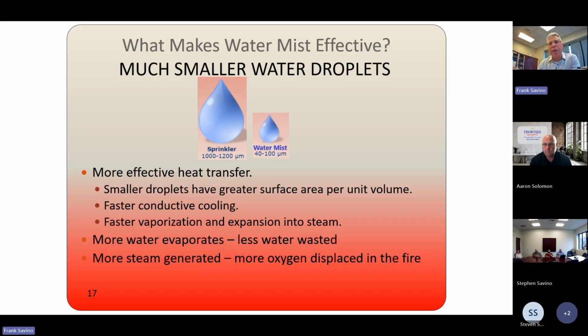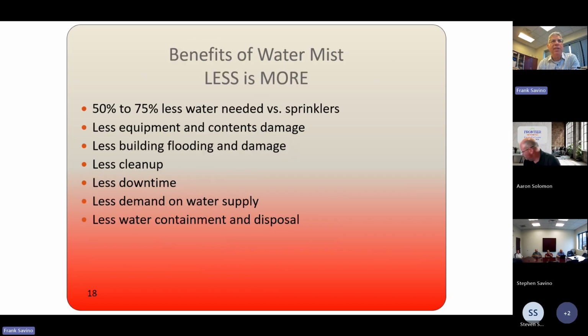And when you think about it, if you look at a sprinkler system discharging water, when it interacts with the burning material and falls on the floor, the water is not doing anything when it's on the floor. So having it in a very tiny form where it can interact with the flame and fully coat the solid burning material, you're really using water in its most efficient way. So you're going to get faster cooling, faster vaporization, and expansion to steam. You get more water evaporating, less water wasted on the floor, and more steam generated. So the benefits, I say less is more. You get 50% to 75% less water needed versus sprinklers, less equipment and contents damage, less building flooding and damage, less cleanup, less downtime, less demand on a water supply, and less water containment and disposal necessary.